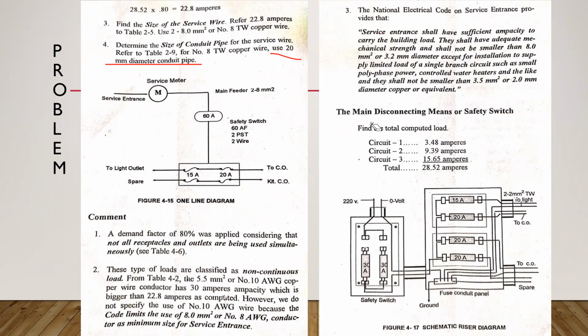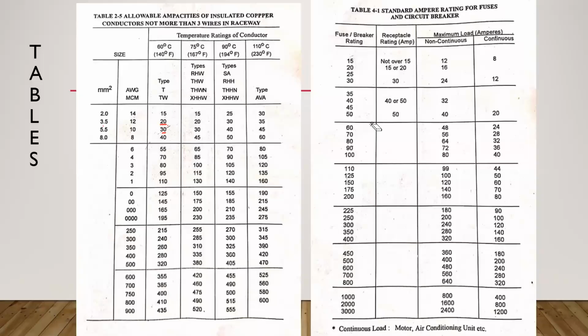So, balik tayo dun sa table. Okay, so ito, di ba, number 8 yung service entrance wire natin. So, fall siya sa 40 amperes. And then, nasa code natin na hindi tayo kung 40 amperes, hindi din yun ang gagamitin natin. Kumbaga, dun sa ating main breaker, dapat yung maximum rated value niya is 40. So, yung 40 na yan, 2/3 value yan siya.